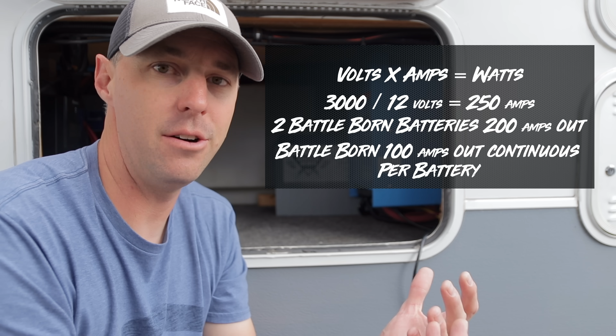With that being the potential demand of the inverter, our two batteries would be maxed out continuous at 200 amps - 100 amps each, wired in parallel, giving us 200 amps at any given time continuous. So at the very least we're maxing out these batteries, and if the inverter overdraws or we have other things on, the BMS in the battery might shut things down to keep the battery safe. Everything would be safe, but we'd be bumping up against that limit the inverter could draw and the RV could be using.